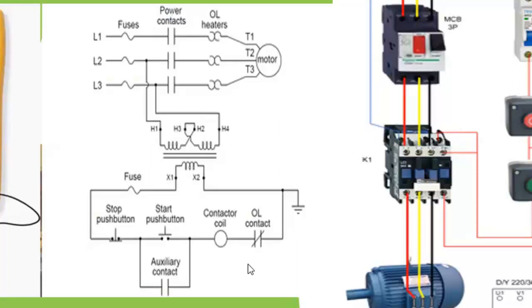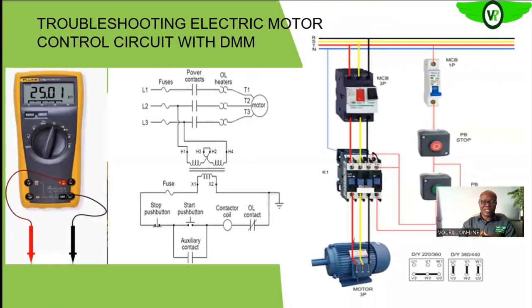Now you can troubleshoot this circuit live or when the circuit is dead, as we earlier explained. The explanations are basically the same. For the additional components, basically you test for continuity, and when you do your AC voltage test, you test before the component whether there is a voltage signal, and after the component whether there is a voltage signal. All of those will help you to zero in on whichever component is causing or may be causing the problem.